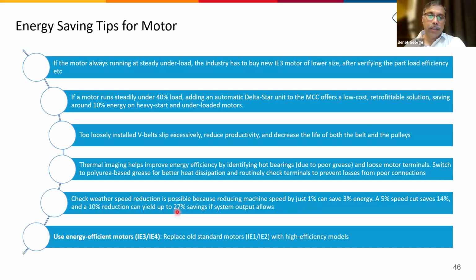So we have to understand what is the efficiency of the motor. So always ensure all the new motors should be IE3 or higher efficiency motors, so that it will reduce the energy consumption. Then, for the motor, you can also think of automatic delta-star changing, or whether it is possible to retrofit. So typically we can have 10% energy saving.